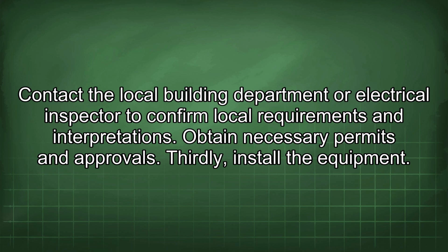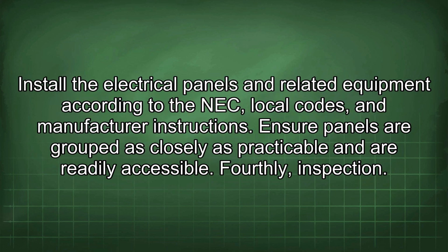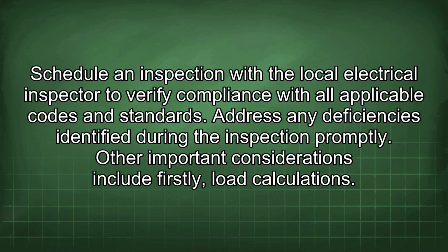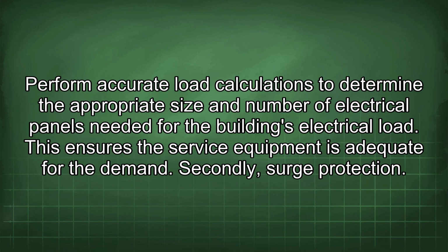Thirdly, install the equipment. Install the electrical panels and related equipment according to the NEC, local codes, and manufacturer instructions. Ensure panels are grouped as closely as practicable and are readily accessible. Fourthly, inspection. Schedule an inspection with the local electrical inspector to verify compliance with all applicable codes and standards. Address any deficiencies identified during the inspection promptly. Other important considerations include, firstly, load calculations. Perform accurate load calculations to determine the appropriate size and number of electrical panels needed for the building's electrical load.